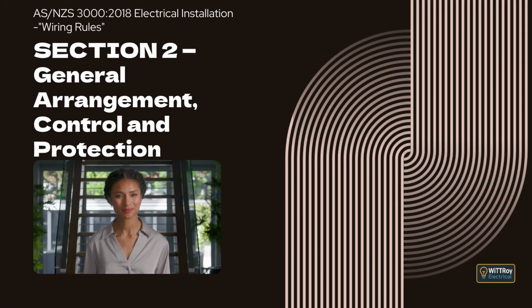Clause 2.5.3.2 Position of overload protective device, general arrangement. This clause explains where overload protection must be placed. Normally, the overload device must be installed at the origin of every circuit and at each point where the cable becomes smaller or its current carrying capacity reduces. There is one general exception. If the conditions in clauses 2.5.3.3 or 2.5.3.4 are met, then the overload device may be placed somewhere else or may be omitted entirely. These exceptions are explained next.